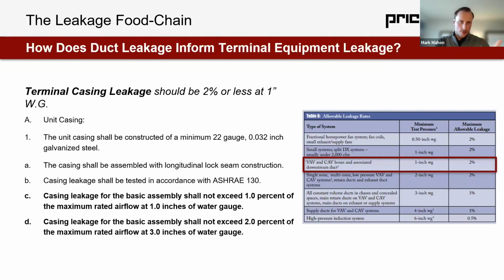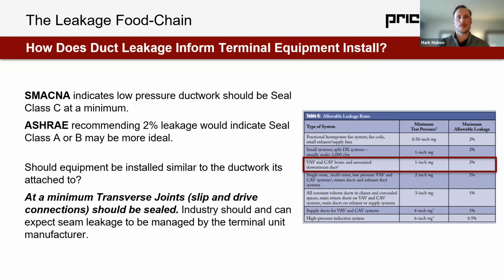So the second question is, how does duct leakage inform terminal equipment leakage? My next question would be, how does duct leakage potentially inform terminal equipment installation? If SMACNA is indicating low pressure ductwork should be seal class C at a minimum, that would mean we definitely need to be sealing transverse joints. So slip and drive connections or the lap joint that we're going to see at the inlet of the terminal. Those need to be sealed at install. However, ASHRAE recommends 2% leakage for the low pressure ductwork system. And that's really closer to a seal class A or a seal class B. And we do see in California, for instance, class A being the requirement.